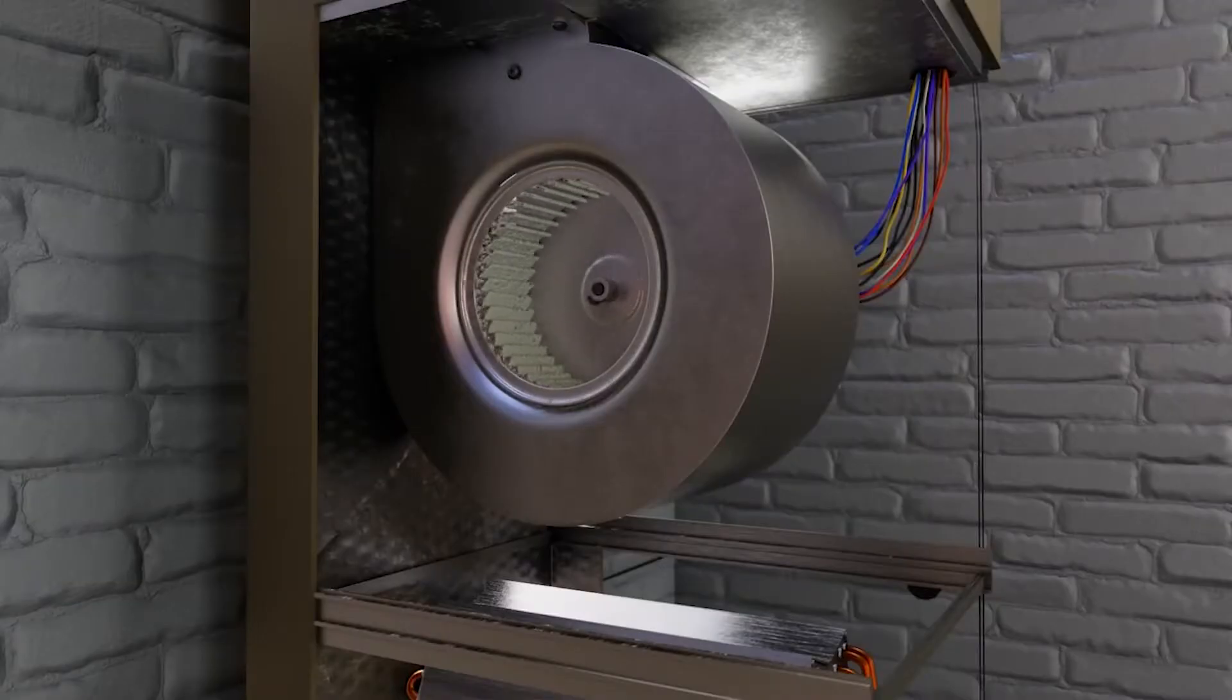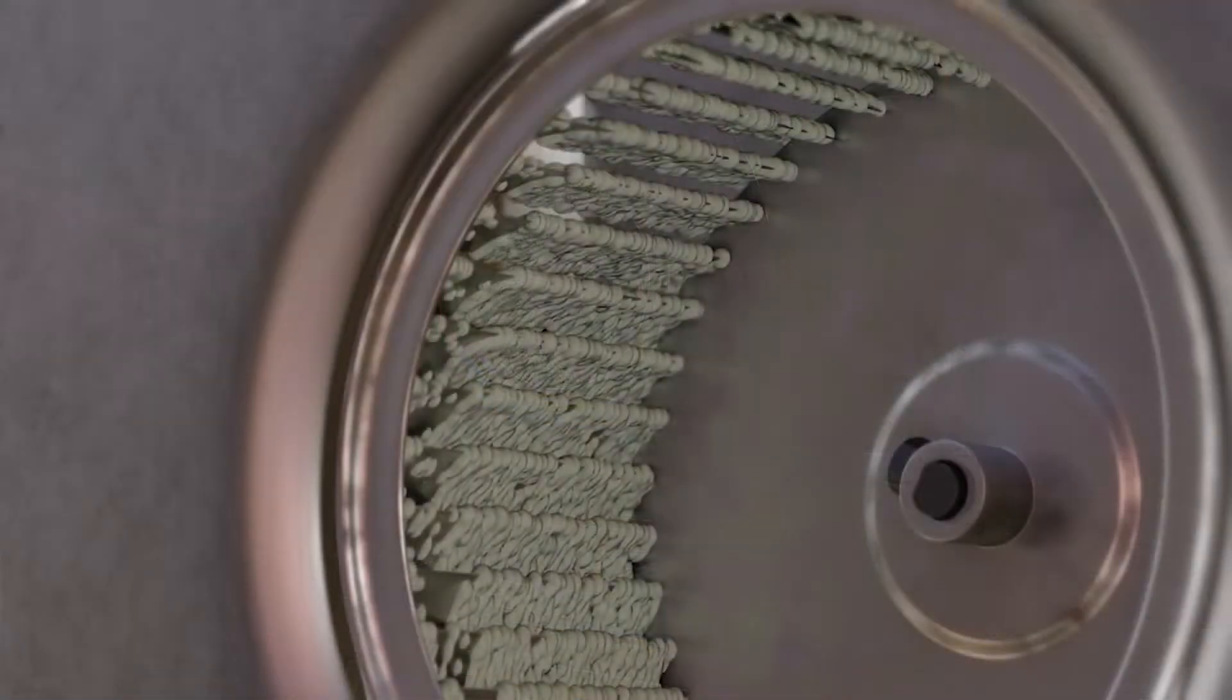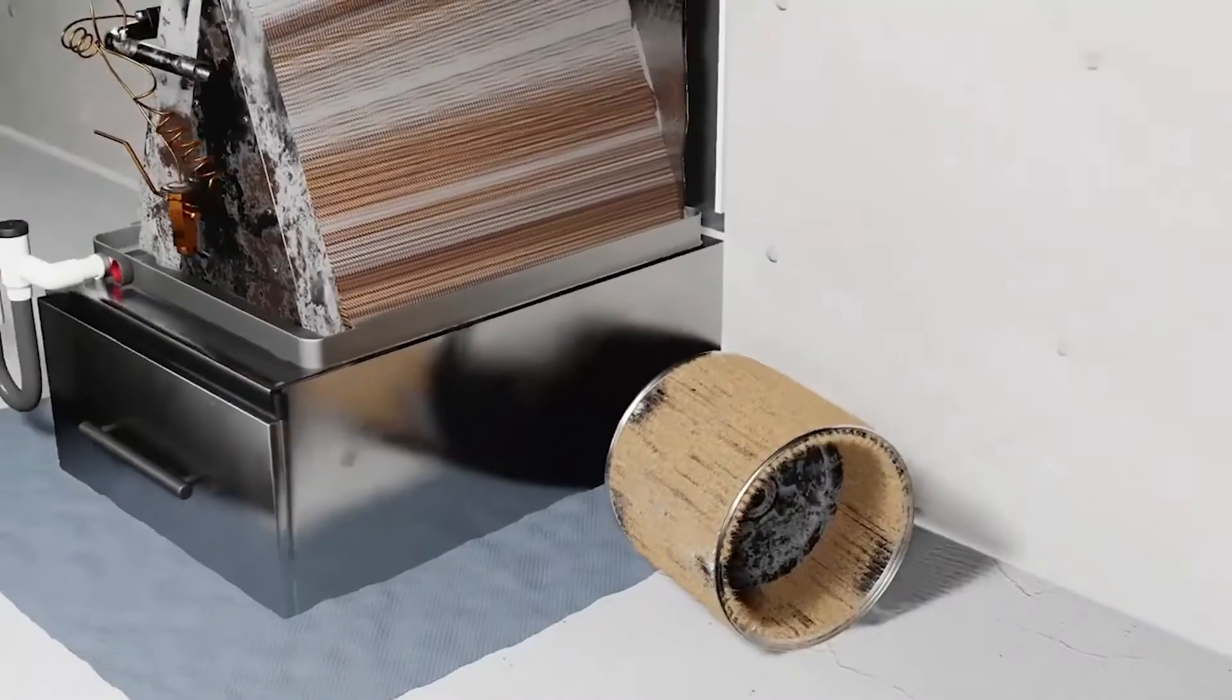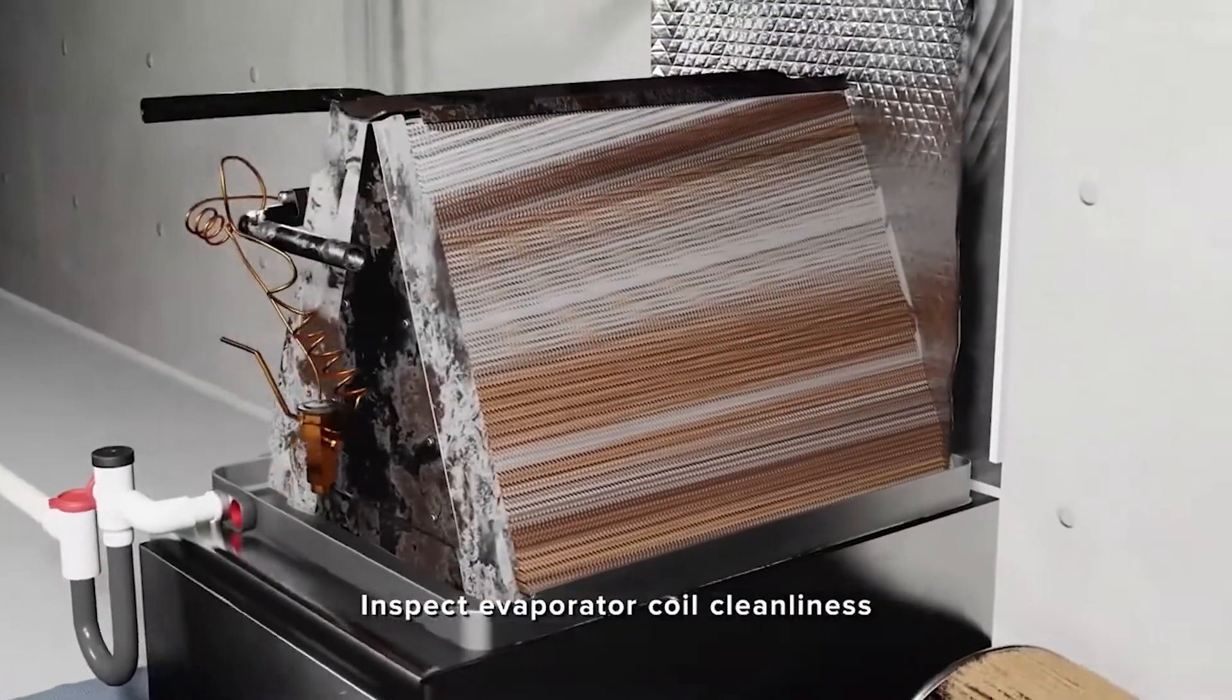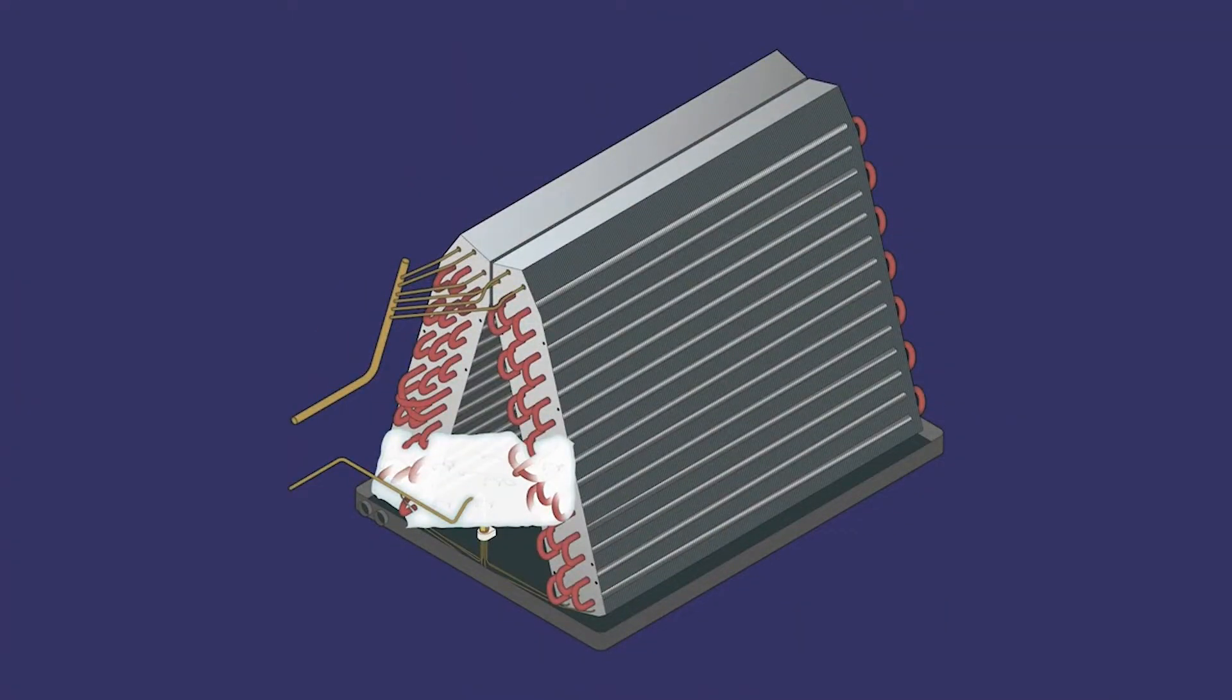Blower wheel cleanliness is critical for system air flow and proper operation. A dirty evaporator coil causes low suction pressure and can result in freezing. It also decreases system performance.